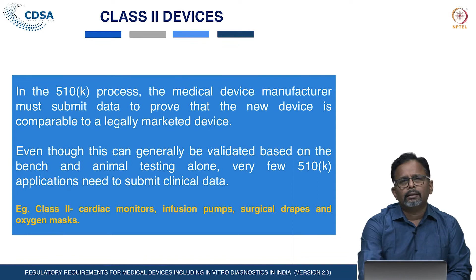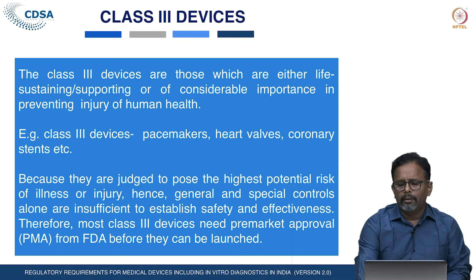Class 3 devices are those devices which are either life sustaining, life supporting, or of considerable importance in preventing injury to human health. Examples of class 3 devices are pacemakers, heart valves, coronary stents, etc. Because these class 3 devices are judged to pose the highest potential risk of illness or injury, the general as well as the special controls alone are not sufficient to prove the safety and effectiveness of these devices, and therefore, class 3 devices need pre-market approval from the FDA before they launch into the market. Without approval from the US FDA, these devices cannot be marketed in USA.